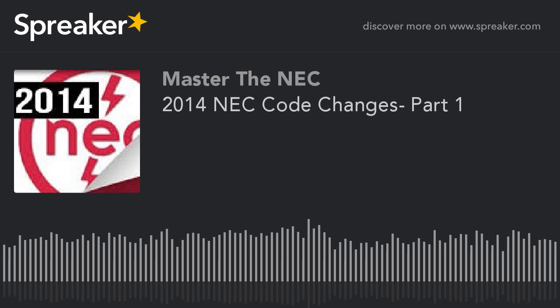It's going to talk about nameplate data information on these modular systems, which is really important. You need to know the loads, the duty cycles, if anything is involved in the equipment, the full load currents, when you have to calculate how you're going to supply power to these things. So you have nameplates that are all associated with it. Now we have some guidance. The branch circuits and feeders that are going to be fed to the different pieces of equipment, all of that is given guidance in here now under 646.7.